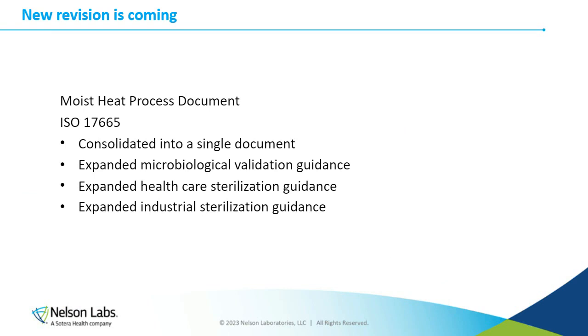One thing to note is that the moist heat document published by ISO is moving into the final draft international stage, so we are very close to publishing the new revision. That new revision will consolidate everything into a single document. It will have expanded microbiological validation guidance, expanded healthcare sterilization guidance, and expanded industrial sterilization guidance, among other things.